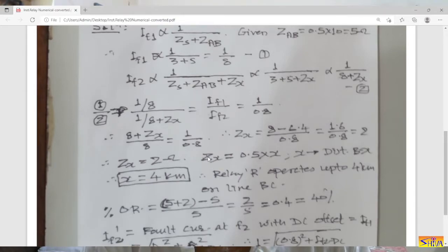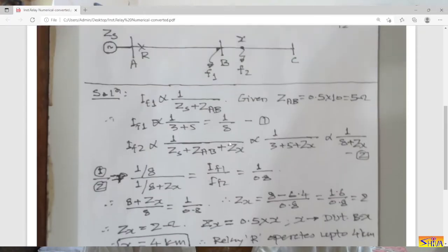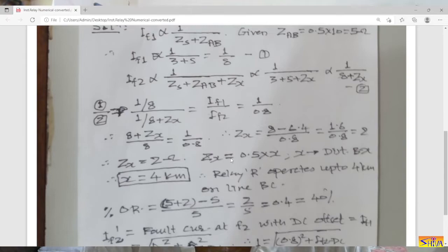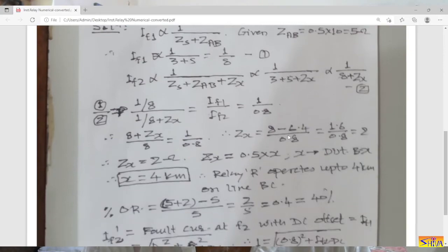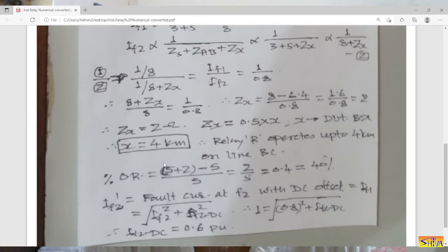ZX = 2 ohms is the impedance of the line from B to X. The line length BX = ZX / 0.5 = 4 kilometers. Therefore relay R operates up to 4 kilometers on line BC — this is the overreach. In terms of transient overreach: (impedance for which relay operates − impedance for which relay is set) / impedance for which relay is set = (5+2 − 5)/5 = 2/5 = 0.4, or 40%.